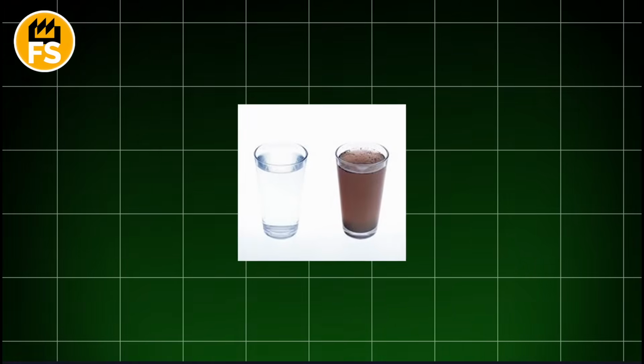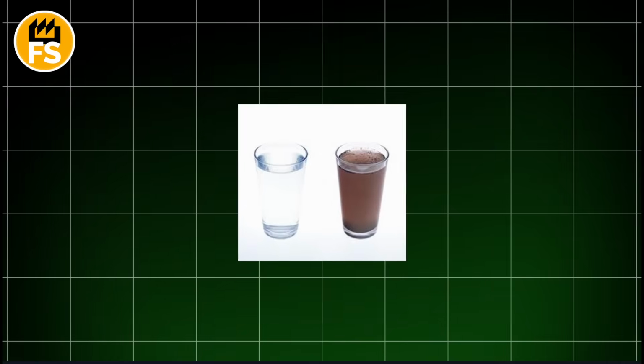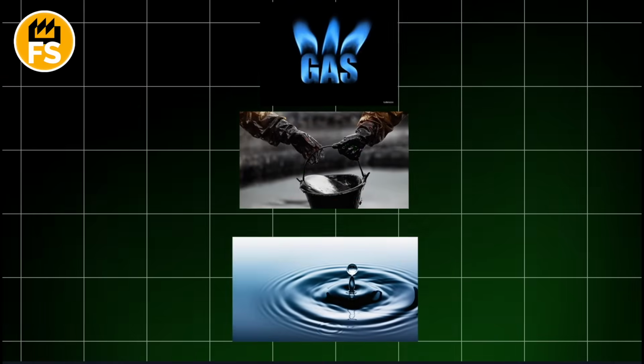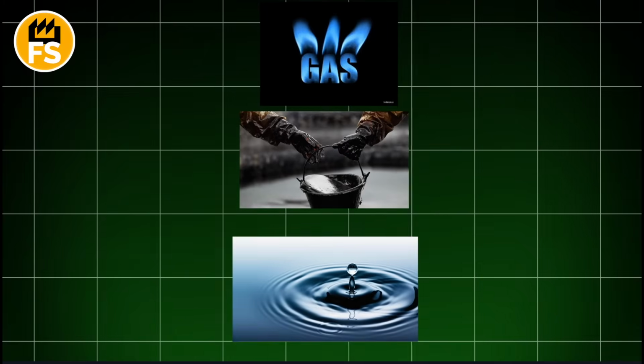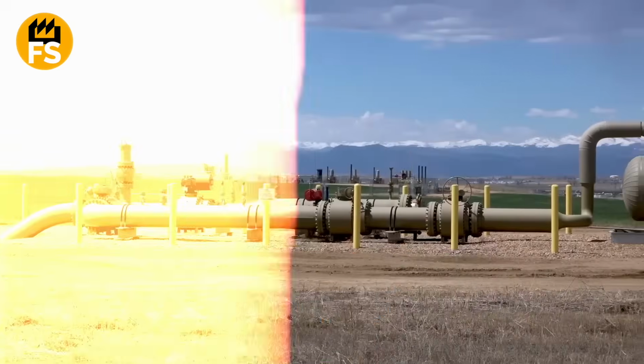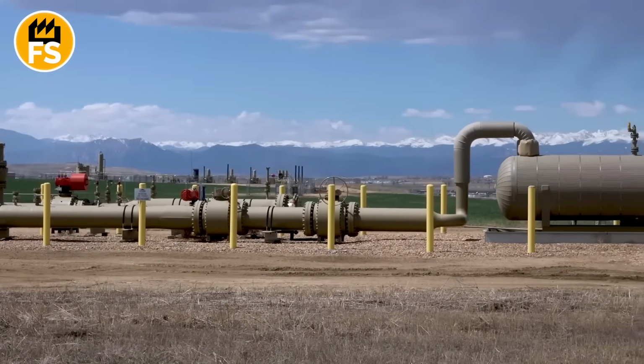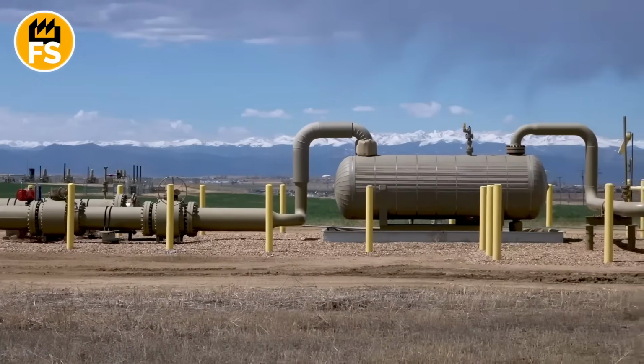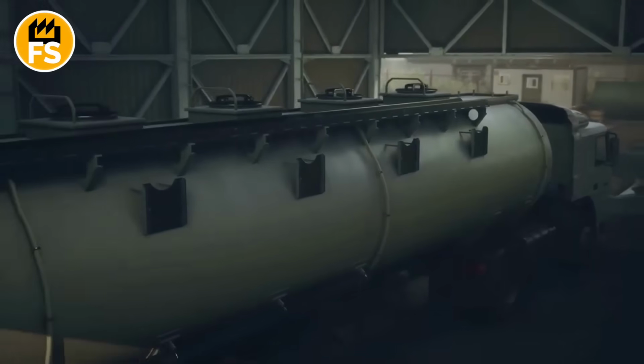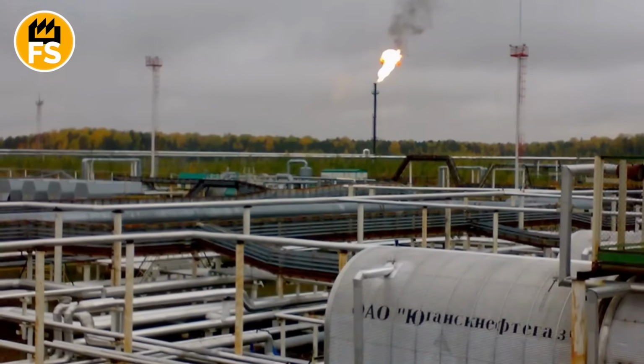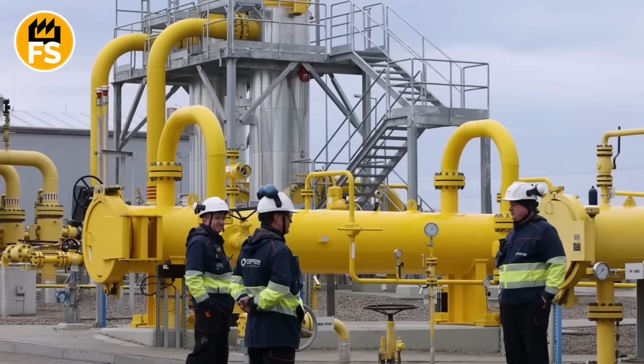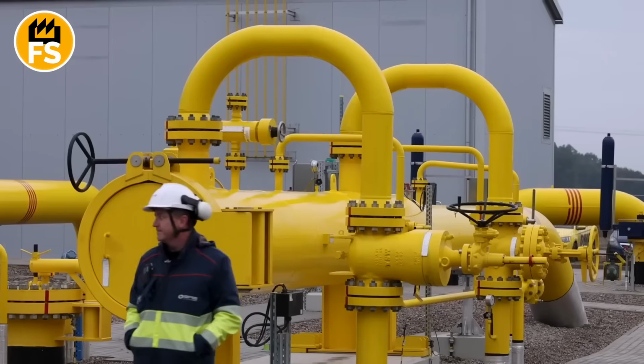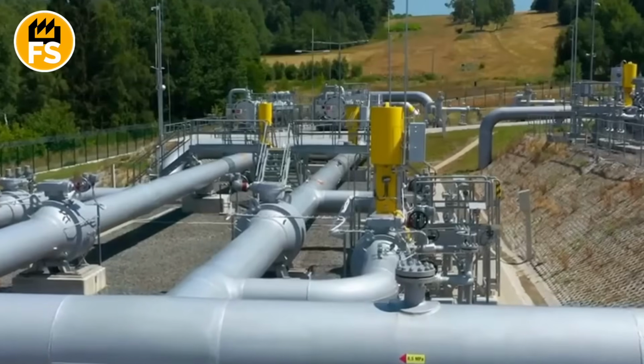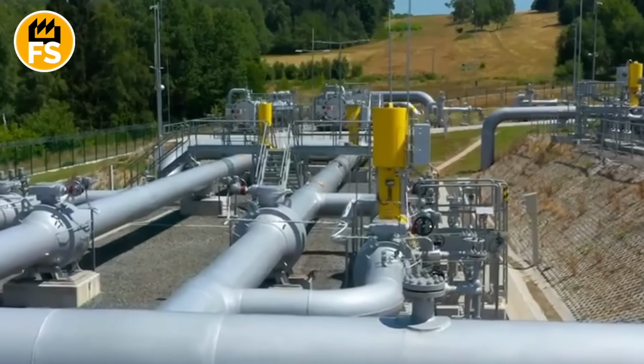Water with salts and fine particles settles first. Oil is lighter than water, but heavier than gas, so it floats in the middle. Methane and other light hydrocarbons rapidly rise to the top. To speed up the process, separators sometimes have inclined plates or cyclone modules installed, which increase the settling area. For example, plates angled at 45 degrees cause oil droplets to coalesce and fall down faster.